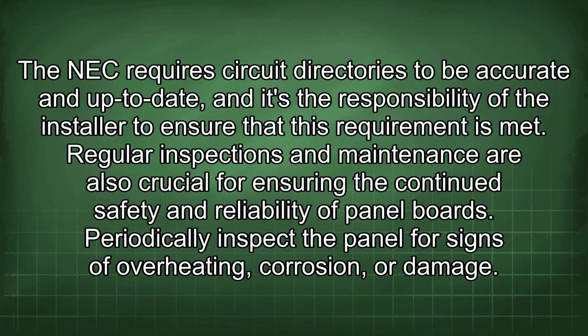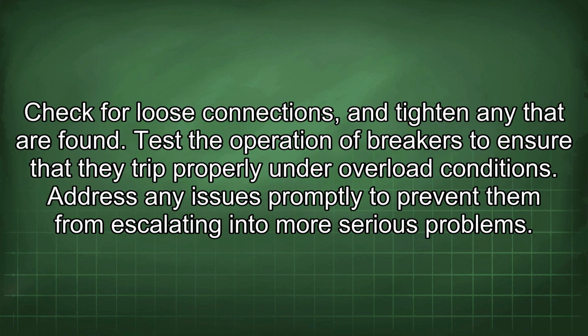Regular inspections and maintenance are also crucial for ensuring the continued safety and reliability of panel boards. Periodically inspect the panel for signs of overheating, corrosion, or damage. Check for loose connections and tighten any that are found. Test the operation of breakers to ensure that they trip properly under overload conditions. Address any issues promptly to prevent them from escalating into more serious problems.